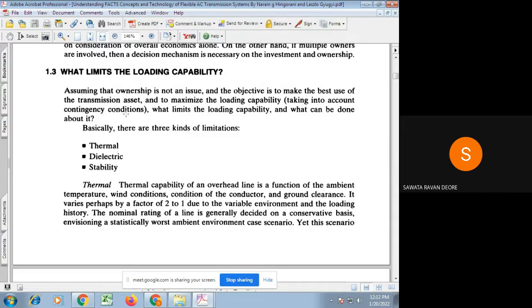So for a given transmission line, according to that current rating and the operating voltage level rating, it has some power handling capacity, and that capacity is called the thermal rating of a transmission line. Obviously, the rated voltage and the rated current of that transmission line depend upon the physical parameters of that transmission line, like, as I said, the type of conductor, size of conductor, then ambient temperature, wind condition, spacing between the conductors, height above the ground, that is, we can call it ground clearance.